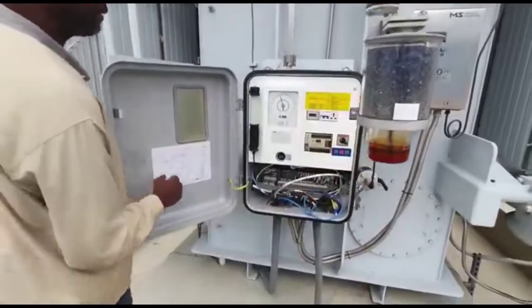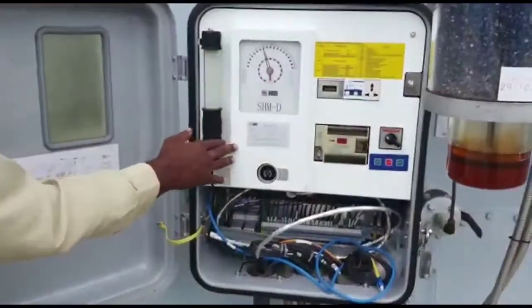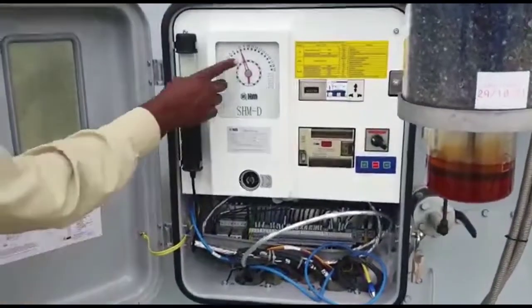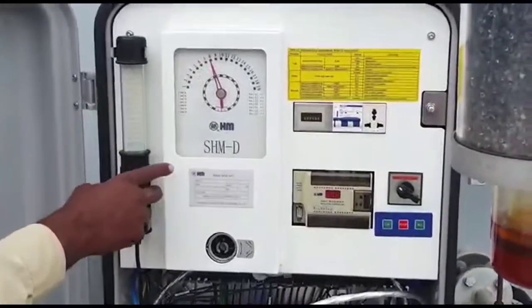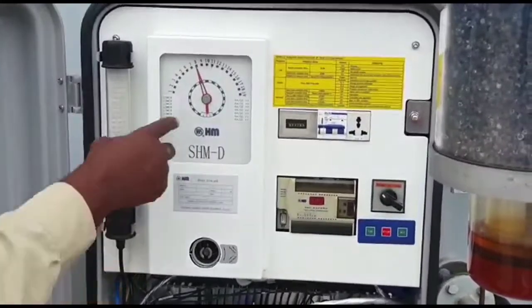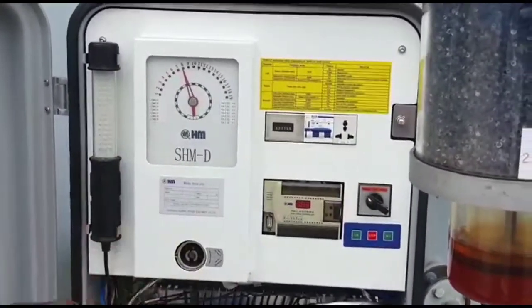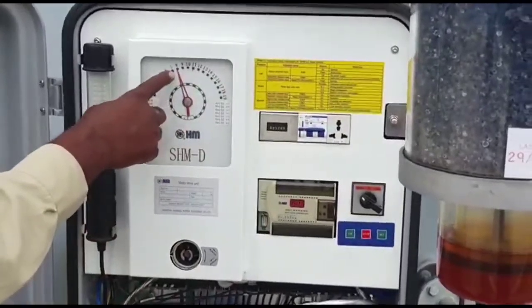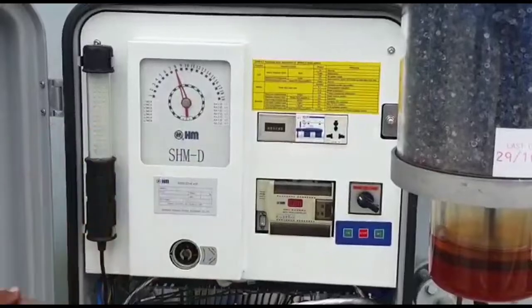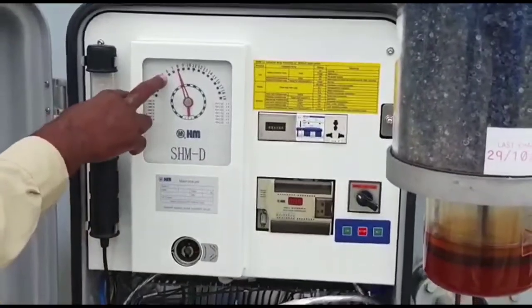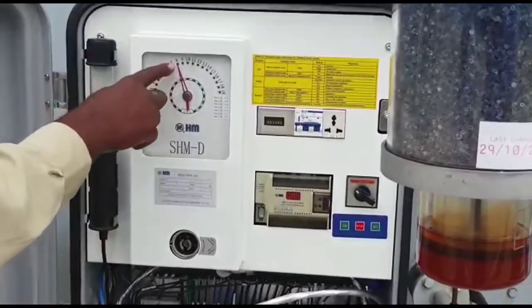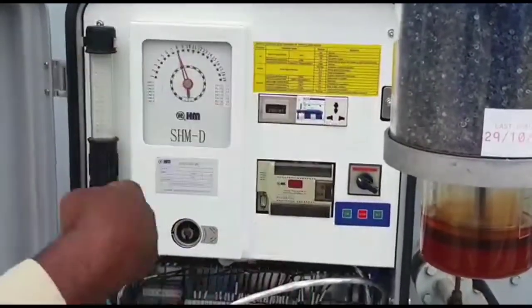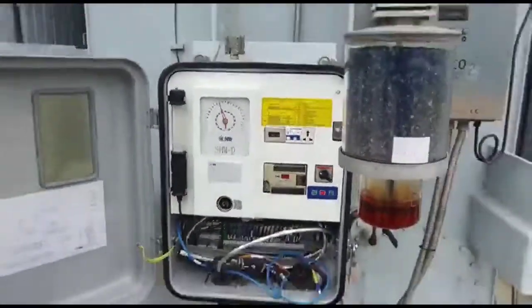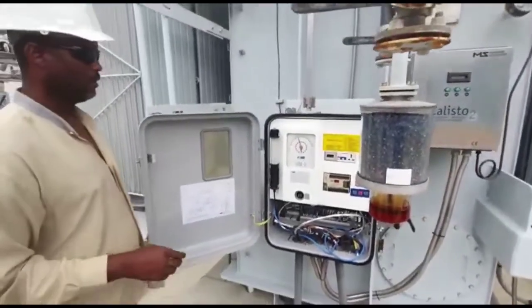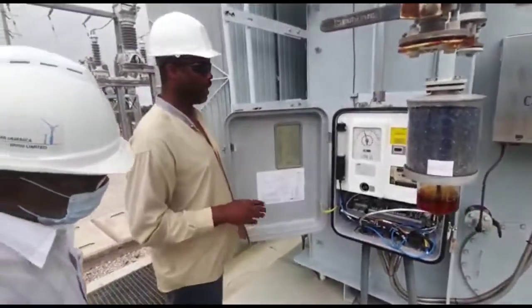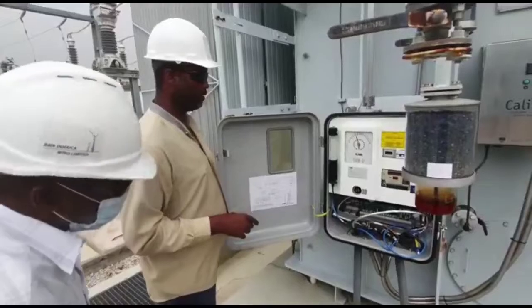So this is inside of it, and this is the outside display of the tap changer. Right now we're at tap 8. If the voltage were to get too high, the tap changer will automatically switch it and it will go down to tap 7. If it's still too high, it will automatically switch it again and go down to tap 6. And vice versa. If it's too low, it will switch it up, and if it's still too low, it will continue switching it up until it reaches the desired value and it will stop. It will stay there until it senses a voltage that is harmful to the transformer, and then it will try to correct that voltage.